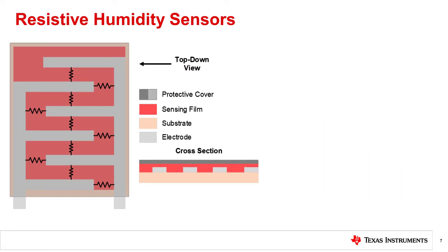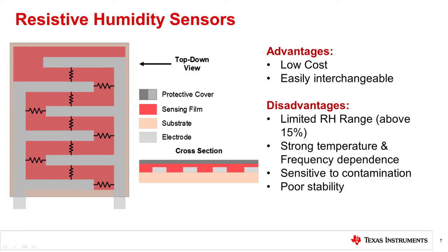Because these resistive humidity sensors are much more easily mass produced than psychrometers, they are typically very low cost. These can also be easily swapped in the field, especially when the linearization is handled by additional integrated circuitry and temperature compensation is already provided. These sensors do have a limited range of effectiveness, including difficulty returning an accurate reading at lower RH conditions. As mentioned, they have a strong dependence on ambient temperature and excitation frequency. Additionally, they are sensitive to contamination by chemicals, so they must be cleaned and manufactured carefully. They also have poor stability under constant conditions. In part, the stability issue is due to resistive self-heating during device sampling and can be mitigated with proper sampling techniques and characterization.